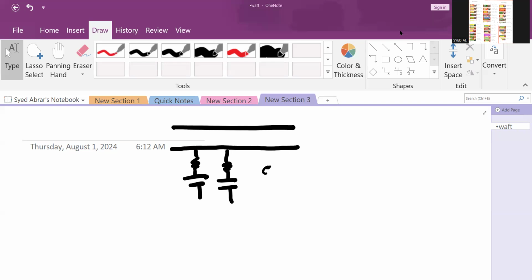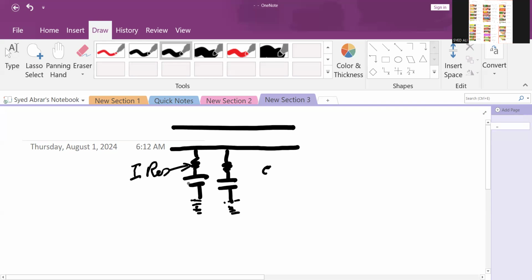Now I have drawn here a diagram of a cable. This is the sheath of the cable, or the PVC jacket of the cable, that I have shown here, this black one. And this here is the ground. So between the conductor and ground, you will have some kind of resistance. This resistance is known as the insulation resistance. Here, they are in parallel. And these are the capacitive leakages, or the capacitive current, which can flow into the ground from this insulation.